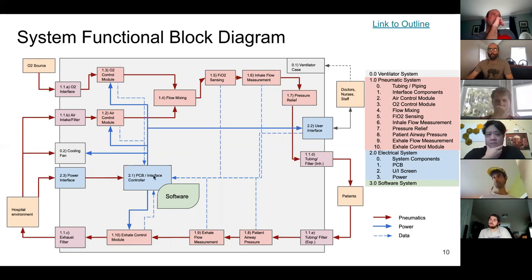Just briefly walking people through it, starting from the external hospital environment: we have the intake air filter, the air control module — my systems engineering speak for the combination of the fan/blower and the air control valve — which is really what's controlling the air pressure and flow rate. That's going into a mixing chamber, which might just be a T in the current design, and I'll talk through the pneumatics in the next slide. We also have the O2 interface, the O2 control module, which does the same thing with the compressed O2. We're going to have a sensing module to get FiO2, a flow measurement subsystem, a pressure relief subsystem, and then a tubing filter interface to the patient.